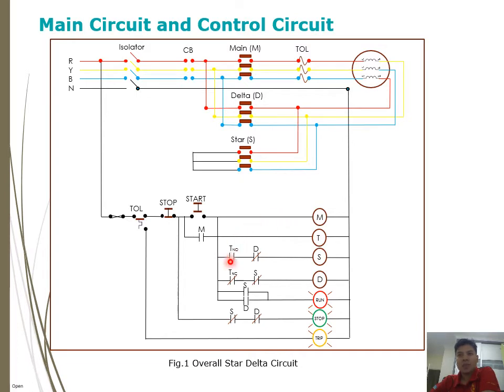Closing this contact and opening this contact — since delta is still open, delta is not energized, and this eventually energizes the star coil. Energizing the star coil opens the delta interlock contact so delta will not be energized. At the same time, energizing S closes the S contact and the motor run indication light will light up.